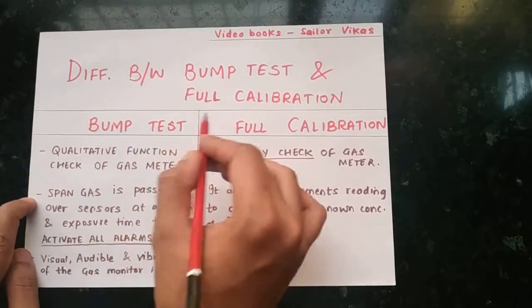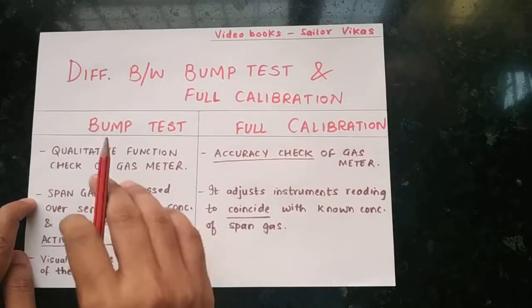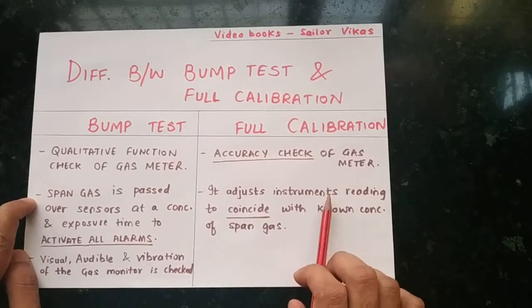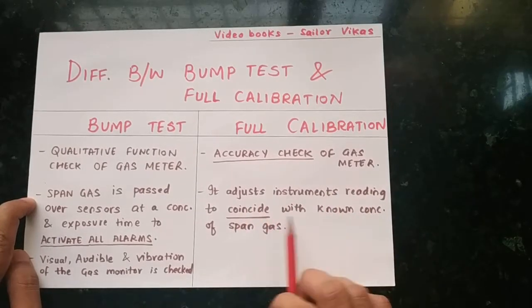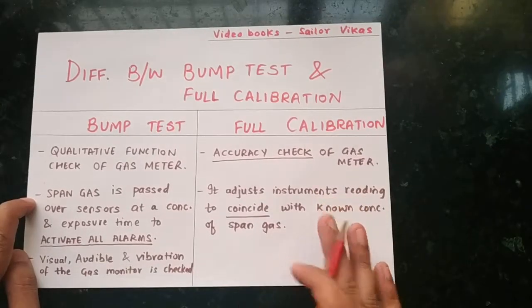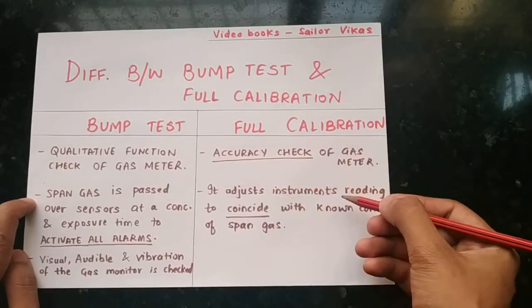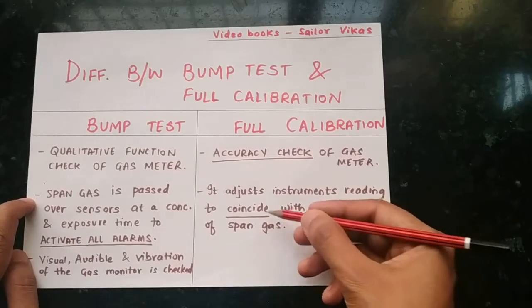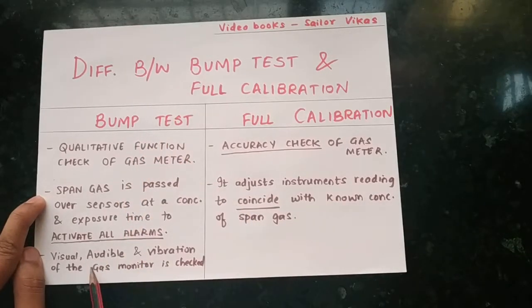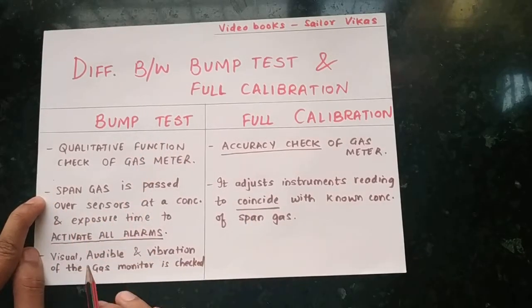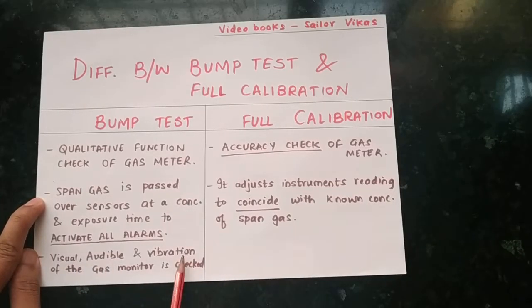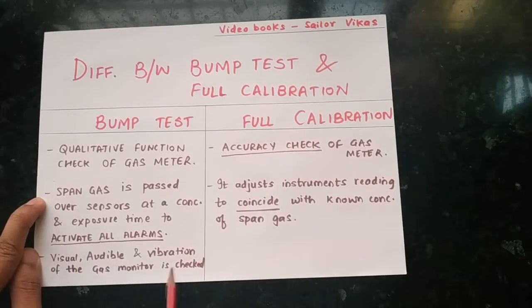In bump test mode, the goal is to activate all alarms. In full calibration, it adjusts the instrument's reading to coincide with the known concentration of the span gas — this is the accuracy check where the readings are adjusted to match the span gas. Bump test is just for checking all the alarms.